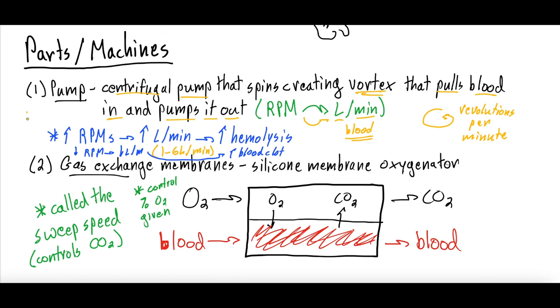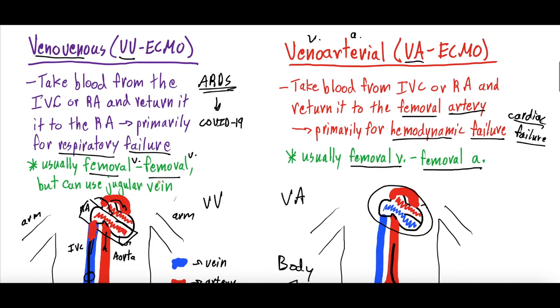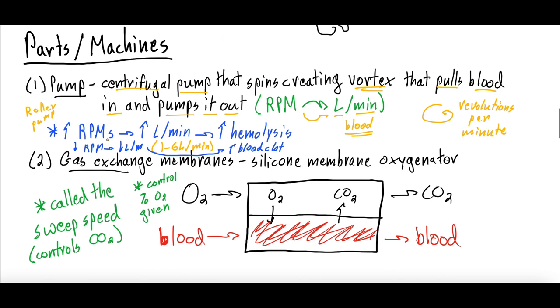There's also a roller pump that compresses the tubing connecting to the centrifugal pump, though it's less relevant in terms of manipulation. The circuit also has a gas exchange membrane, or gas exchanger. For VV ECMO this is critical — you need to oxygenate the blood and pull out carbon dioxide. For VA ECMO the pump is most important, but the gas exchanger still matters. This is a silicone membrane.